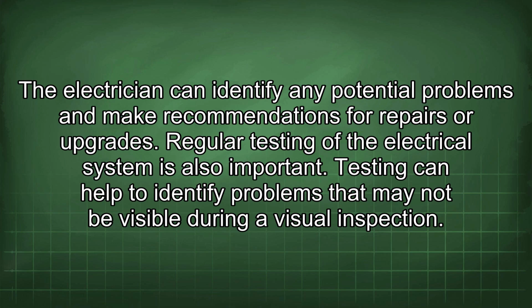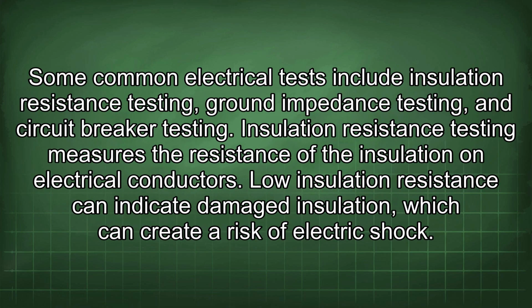Regular testing of the electrical system is also important. Testing can help to identify problems that may not be visible during a visual inspection. Some common electrical tests include insulation resistance testing, ground impedance testing, and circuit breaker testing. Insulation resistance testing measures the resistance of the insulation on electrical conductors. Low insulation resistance can indicate damaged insulation, which can create a risk of electric shock.